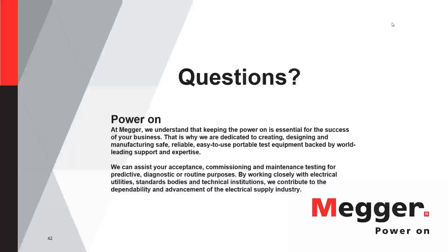Okay. Thank you, Robert. Next question comes in from Christopher. Is there a rule of thumb for the cable length for the arc reflection fault detection method? And are these tests destructive? I think I'll start this one off. Rule of thumb, and Henning was talking about this in just the last question with the wind farms. The TDR itself will go very far, 20,000, 200,000 feet or more sometimes.